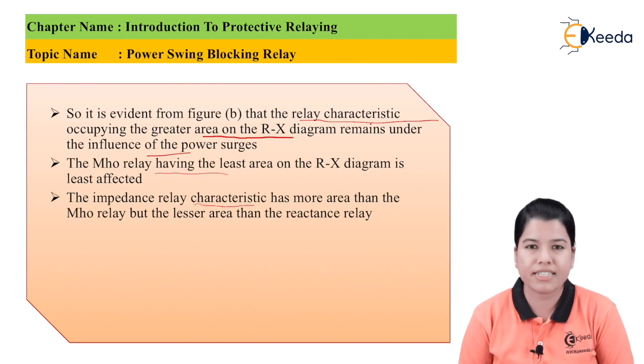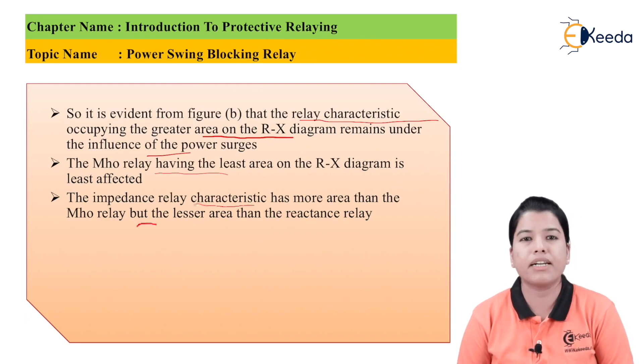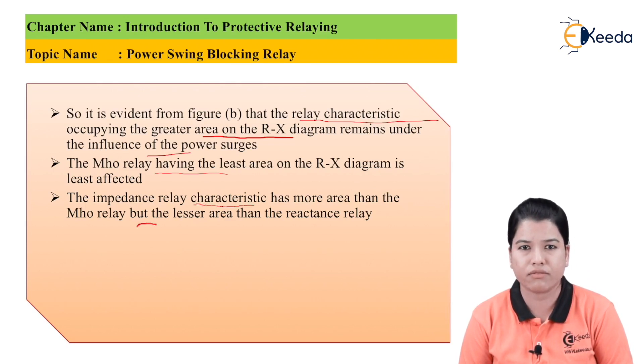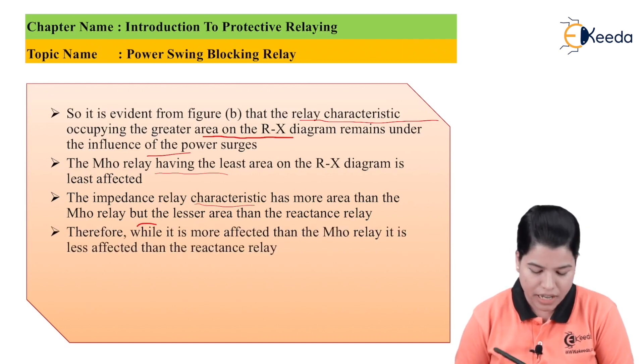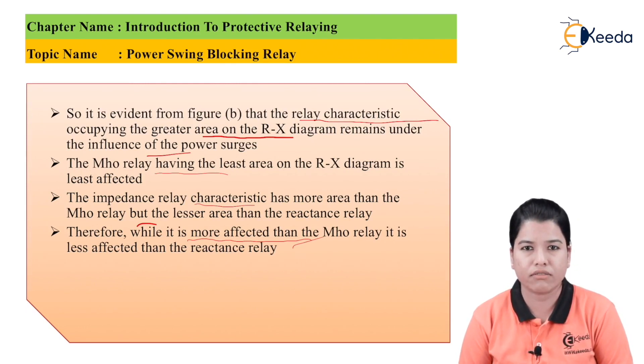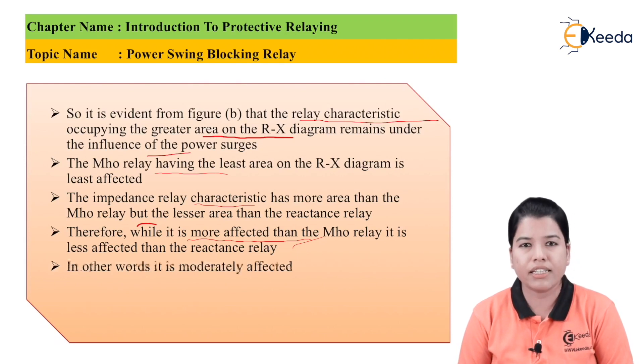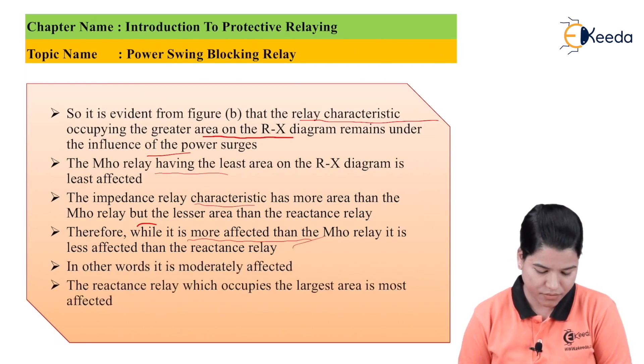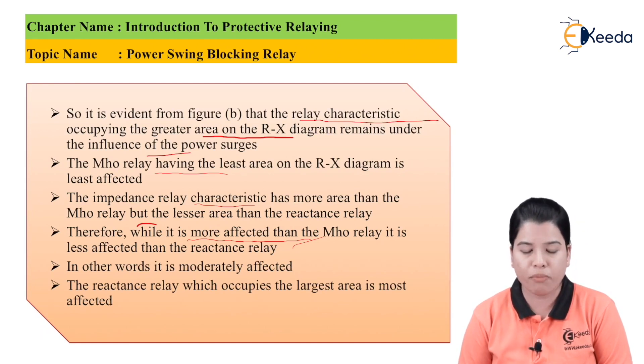The impedance relay characteristic has more area than the Mho relay but less area than the reactance relay. So the impedance relay will be affected more than the Mho relay by power surges, but not as much as the reactance relay — it is moderately affected. The reactance relay occupies the largest area and hence is the most affected by power surges.